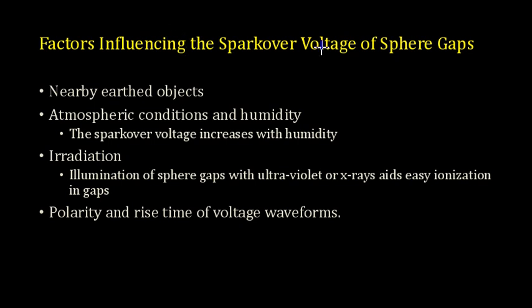Now there are many factors that influence the spark over voltage of sphere gaps. First one is nearby earthed objects. If you have nearby earthed objects, it will reduce the flashover voltage, because you will get a conducting path nearby, so that the sphere gap will be breaking down at a lower voltage. It will break down before even the flashover voltage is reaching near the flashover voltage of this particular air gap, if you have nearby earthed objects.